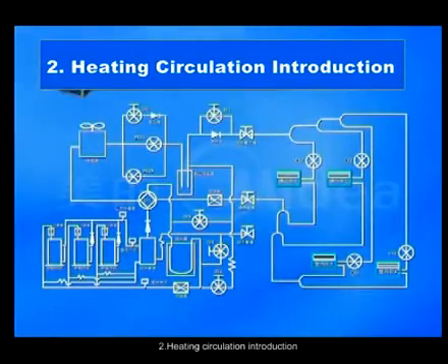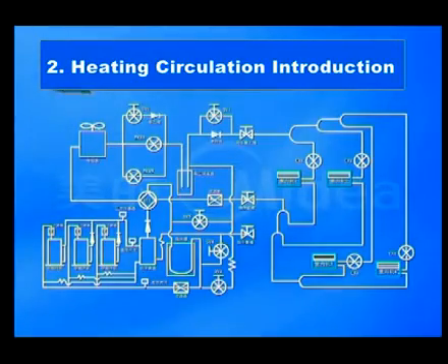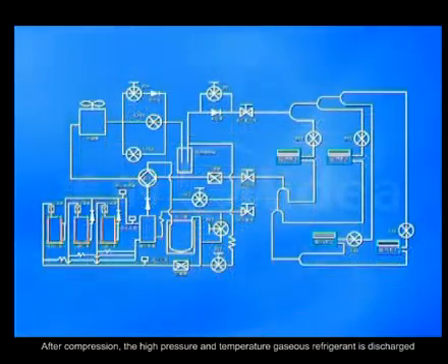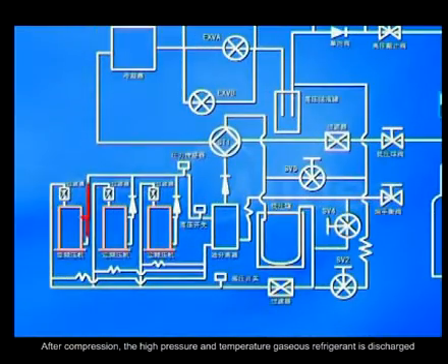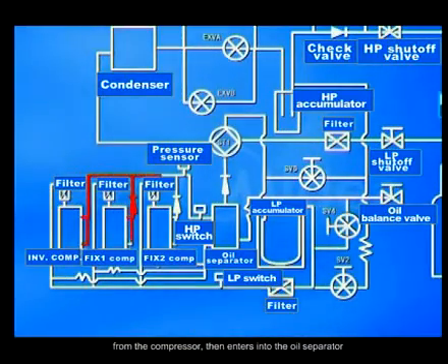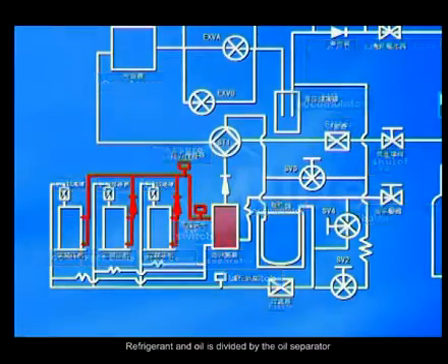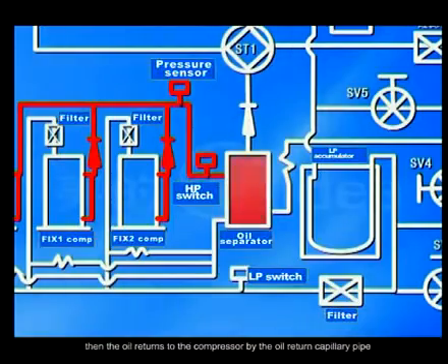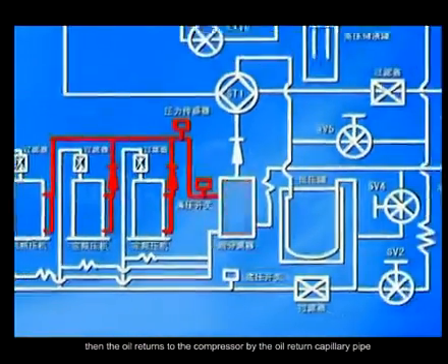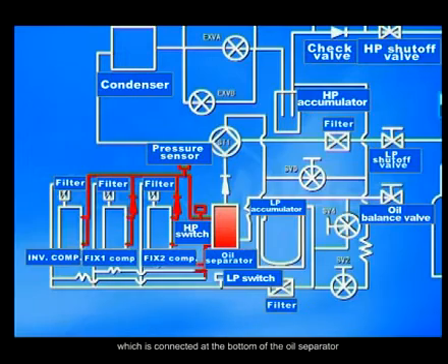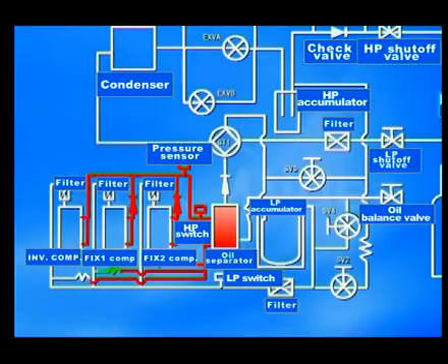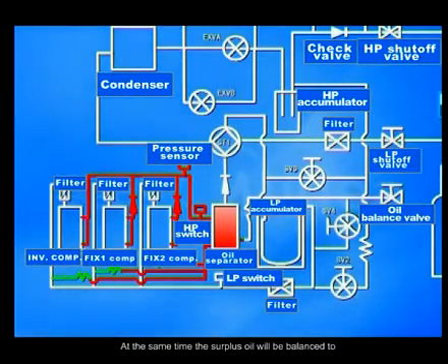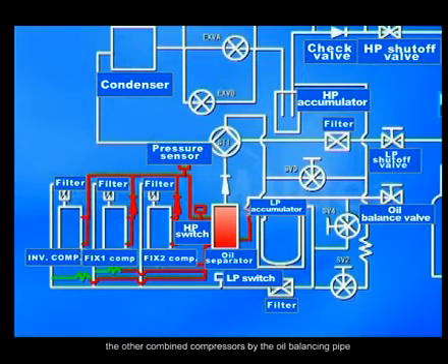Two, heating circulation introduction. After compression, the high-pressure, high-temperature gaseous refrigerant is discharged from the compressor, then enters the oil separator. Refrigerant and oil are divided by the oil separator. Then, the oil returns to the compressor by the oil return capillary pipe, which is connected at the bottom of the oil separator. At the same time, the surplus oil will be balanced to the other combined compressors by the oil balancing pipe.